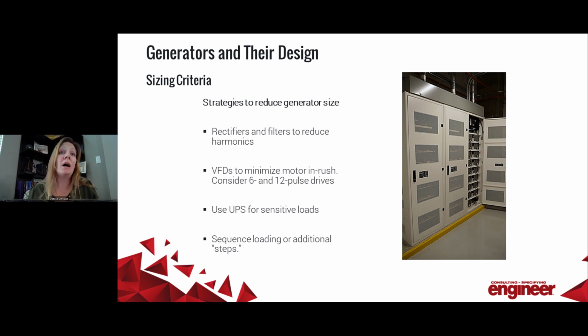Another strategy is to apply an uninterruptible power supply system that will not only provide uninterruptible power to the critical loads, but it also provides cleaner power through the use of more filters and rectifiers to the loads, making them less susceptible to the voltage dips and transients on the generator. It basically will act as a barrier to ride through those anomalies while it's using its DC power. So these strategies, combined with plugging in as many load steps as you possibly can, will aid in the overall right sizing of the system.